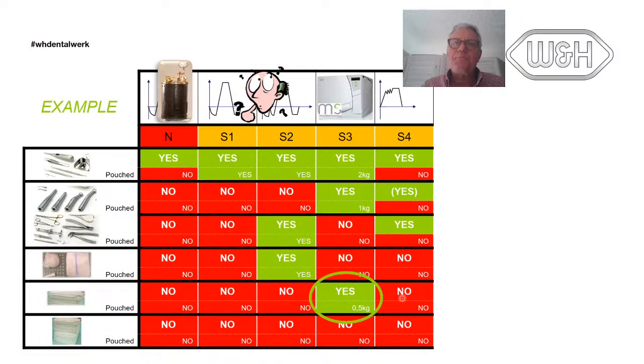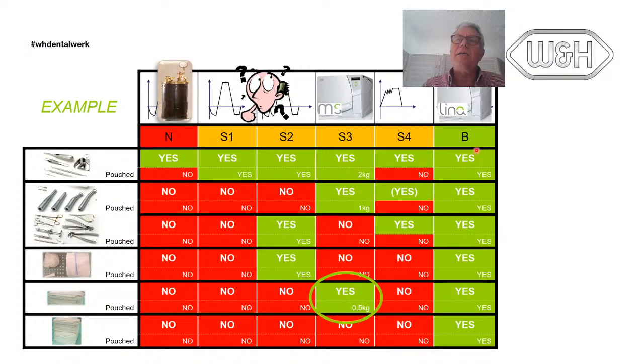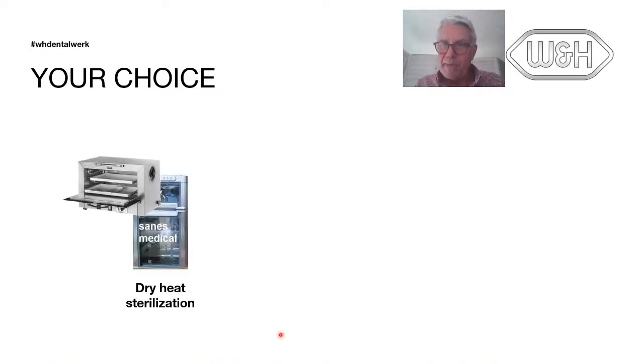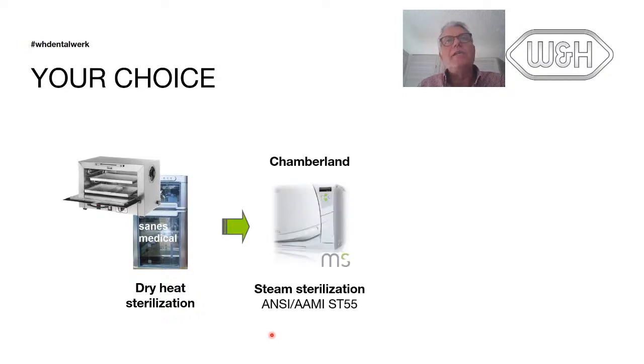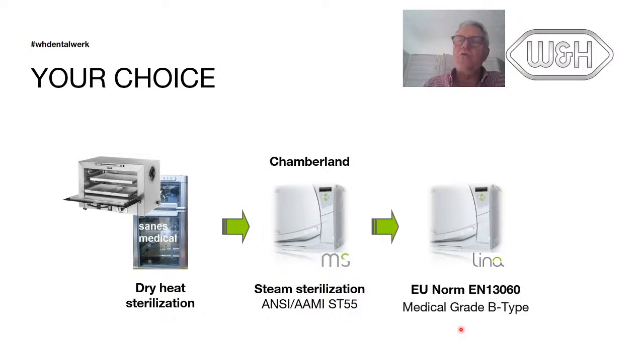This is the hospital medical grade cycle. You can process everything. So now your choice could be to switch from your dry heat. You know, in my country it is forbidden because of the lack of reliability and the impossibility of processing all the instruments. So it's forbidden in my country and most of the European countries. You may switch to, this is a mistake, you must switch to MS. This machine complies to the American standards, ST55. And this machine, which we call medical, surgical, if you do implants, I would really recommend to go for Lina. I know we equip your markets with some Linas and people are very happy with Lina.